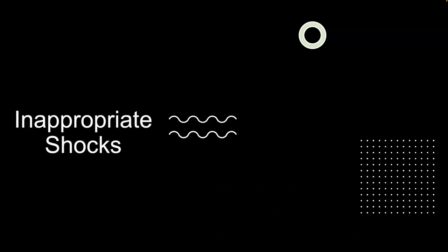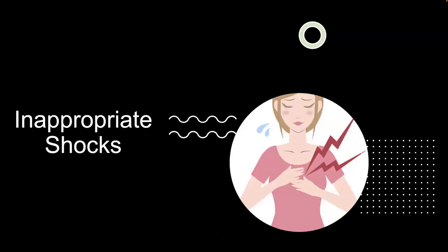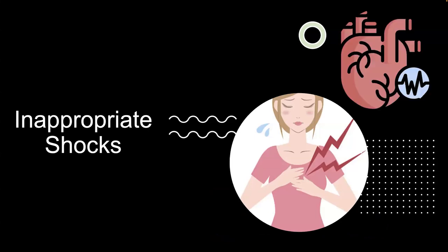However, the ICD device will not always make decisions correctly. This is because the decision algorithm usually requires very high sensitivity. The high sensitivity helps the ICD not miss any cases requiring a shock. However, there will be a lot of inappropriate shocks from the ICD device, and these inappropriate shocks lead to various health issues, including pain, increased risk of arrhythmias, and anxiety.